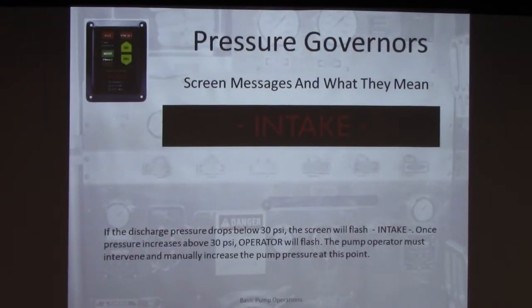Because remember what the pressure governor does. Its intent is to protect the pump. So it will automatically slow it down if it senses that the supply pressure is getting low, right? In any other situation, you would have to notice that, and you would have to shut down the pump, right? But it doesn't, but you would know that that's going on. So you would be able to alert the crews that are inside the building to say, hey, there's a problem.